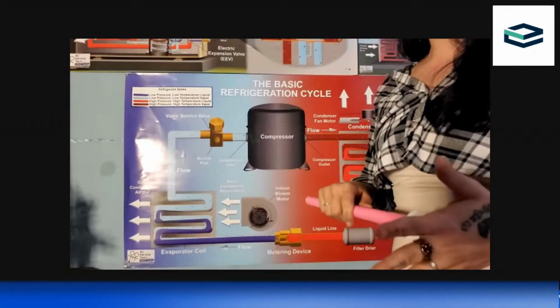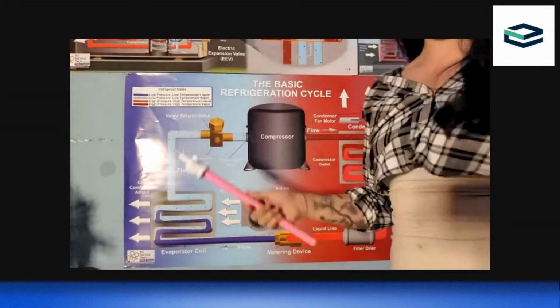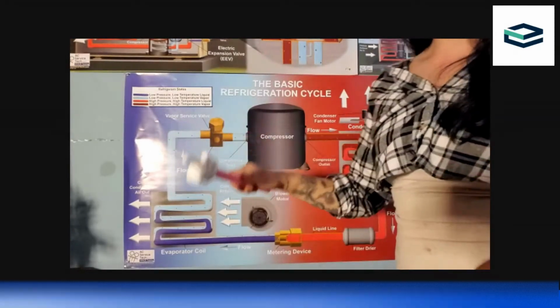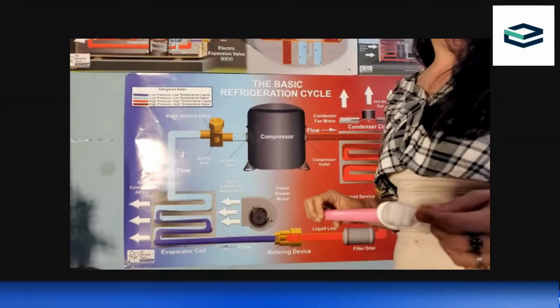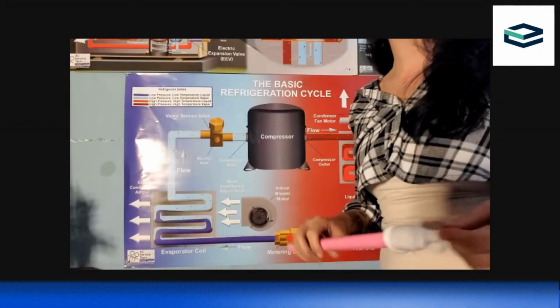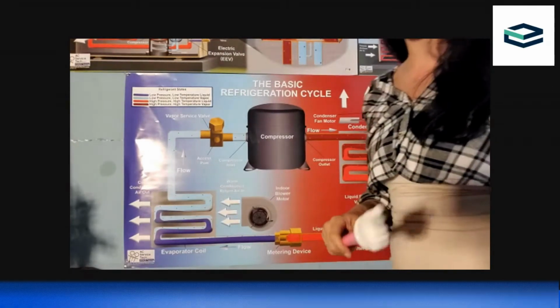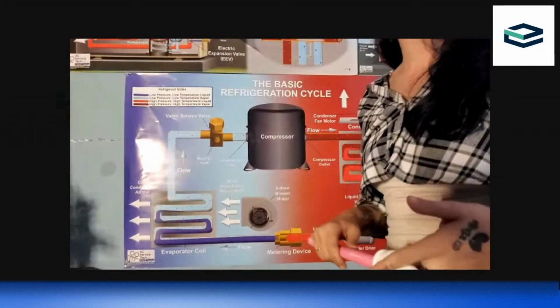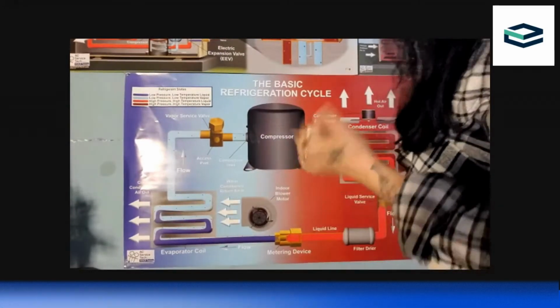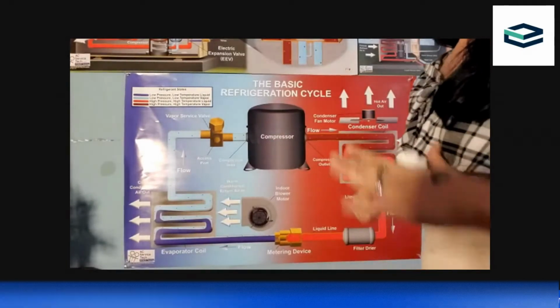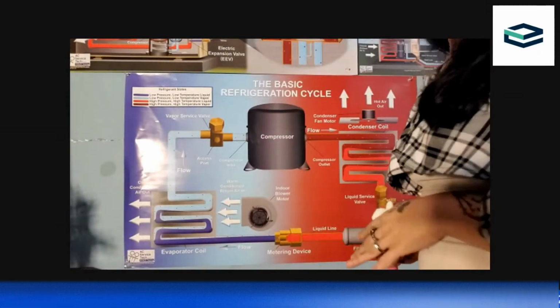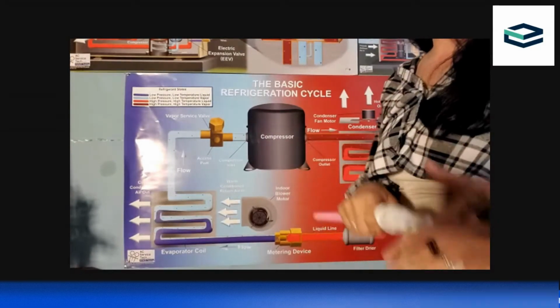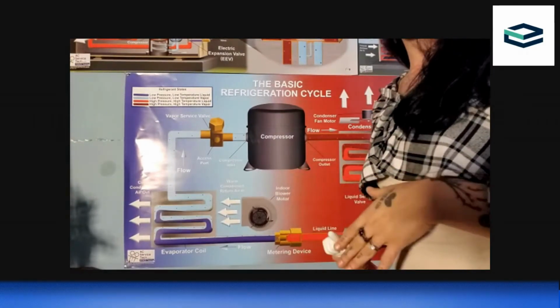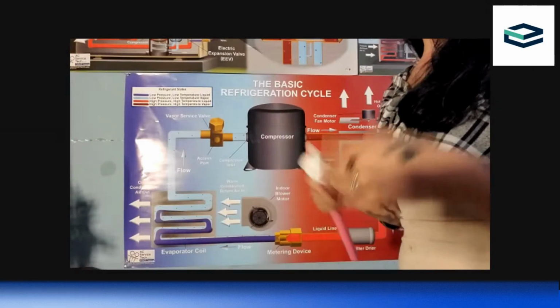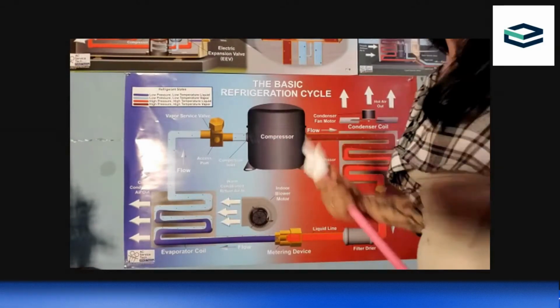So that's why, if you guys have heard anything about HVAC, I'm sure you have as maintenance techs, about what's happening right now, we are switching completely over to A2Ls, which are 100% better for the environment. They're very low GWP. A lot of them are natural refrigerants. A lot of the ones that are coming out after the A2Ls are natural refrigerants as well. Okay, so knowing that, we're going to go with 410A, which is an HFC, also not harmful to the ozone, but it has a high global warming potential. So it raises the temperature of the atmosphere and it's a greenhouse gas.